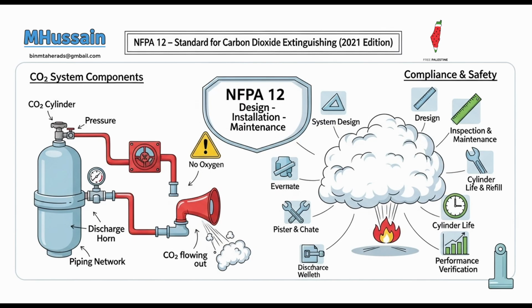Yes. What's fascinating here is the design dilemma. Sometimes a system designed for surface fires might be chosen due to initial cost. Cheaper option. But if a deep-seated fire develops, there's a significant risk of reflash once the initial agent dissipates because it hasn't cooled the core. Save money upfront, risk reignition later. It's a critical decision that weighs initial cost against the ultimate level of protection against all potential fire types.